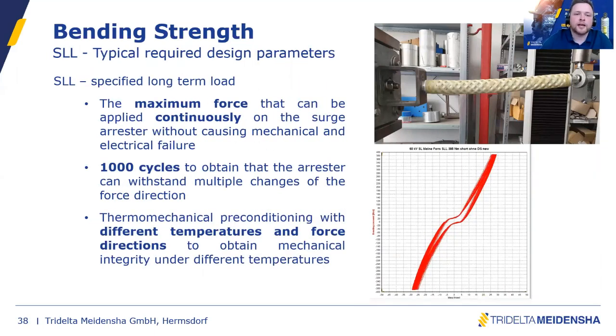Then we have the SLL value, don't mix them up. Specified long-term load, normally this is lower than the SSL because this value is the maximum force that can be applied continuously, not only for a short time. And this specific value is tested in a 1000 cycle test. So the surge arrestor is bent up and down 1000 times. And it has to be electrically and mechanically good after the test.